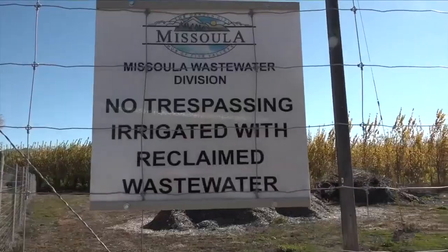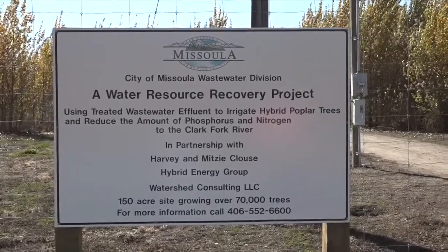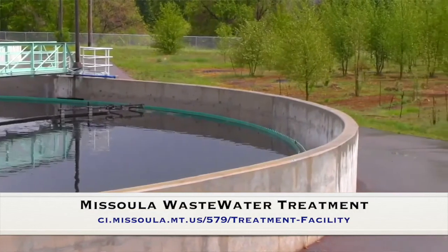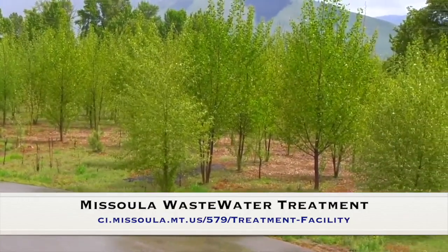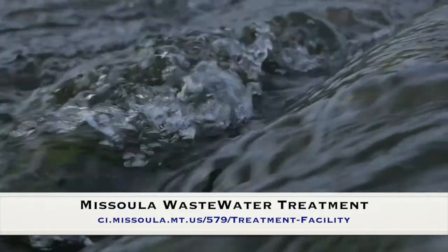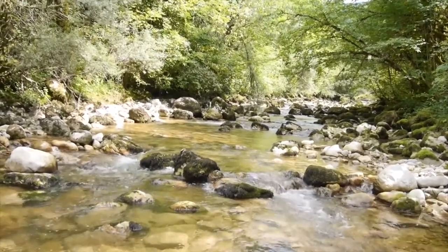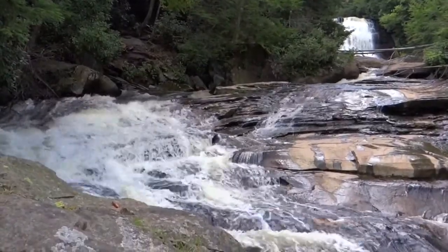We're in an unusual place — we're in a forest of poplar trees. The city leased this from Harvey and Mitzi Klaus four years ago to grow these trees. The primary purpose is we take out about a million gallons of treated effluent a day to water these trees between May 1st and September 30th. Although we have high quality effluent we discharge to the Clark Fork River, this takes out about 20 to 25 percent more phosphorus and nitrogen from the river during the summer months — that's the algae growing season. This is a very economical way to keep nutrients like phosphorus and nitrogen out of the Clark Fork River and put it to beneficial reuse.